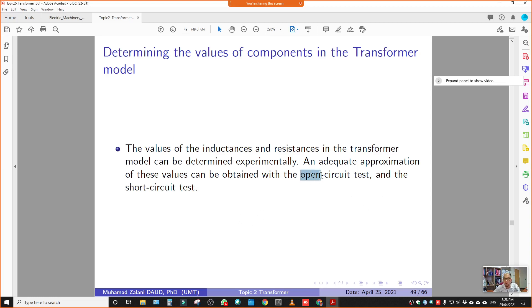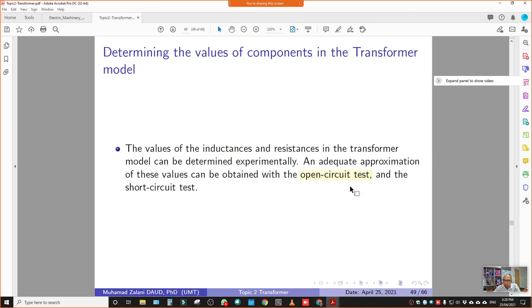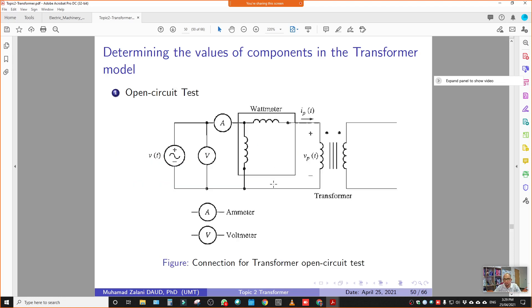What we do is conduct the open circuit test and the short circuit test. These are the two methods used to determine the values of the transformer model — meaning the values RS, RP, XS, XP, XM, and RC. All these values can be determined using the open circuit test and the short circuit test.